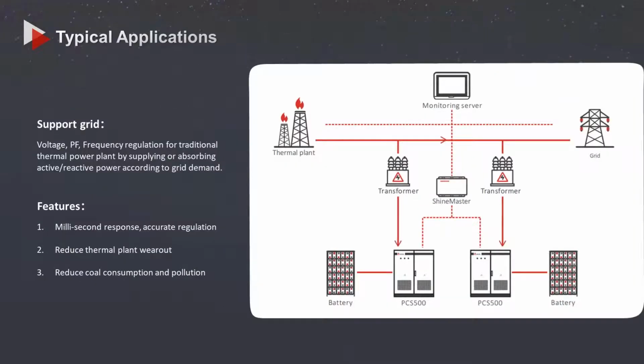Next, let's take a look at some application scenarios of PCS and see how PCS is applied in our actual lives. This system is used on the power generation side of the grid. In order to ensure stable power consumption at the load terminal, the energy storage system can smooth the output curve by absorbing and releasing electrical energy to make up for the lack of power supply. And it can also participate in the primary and secondary frequency modulation requirements of the grid.